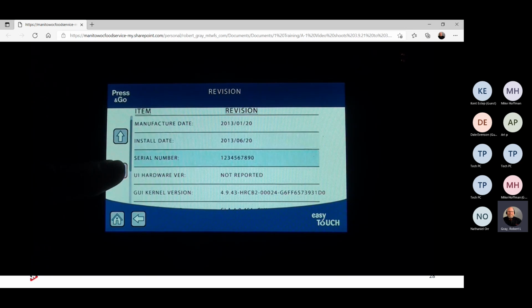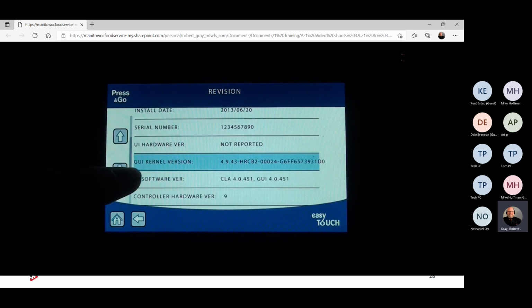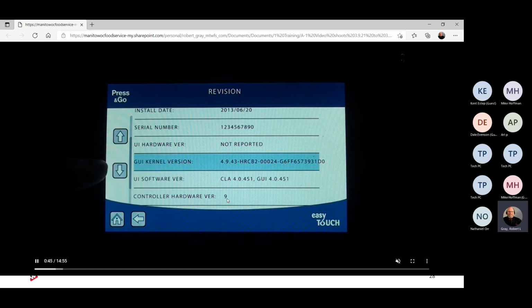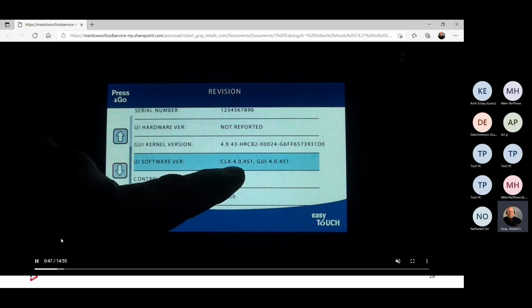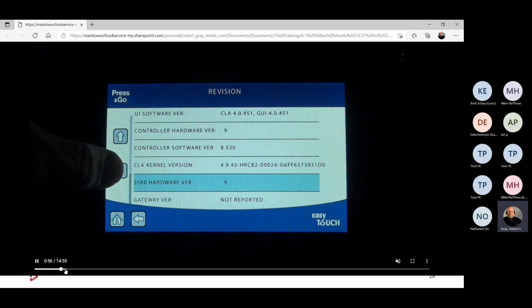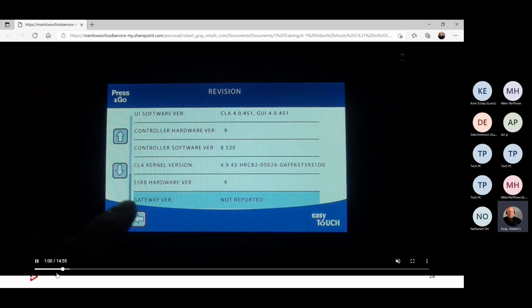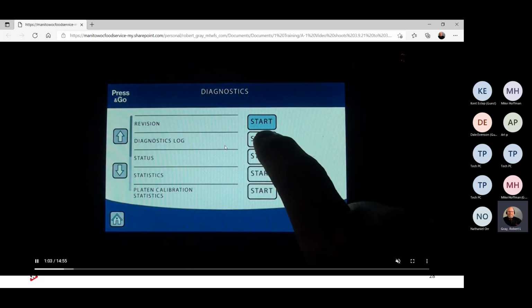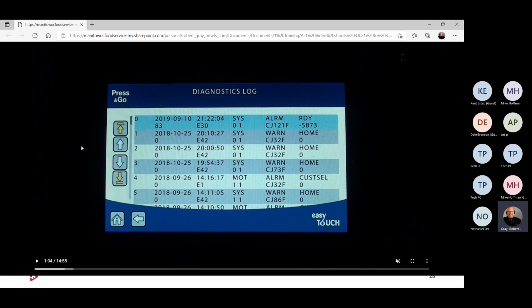Serial number, you're going to check the serial number. Is it correct? Yes or no? If it's not, you have to change it. Again, just all the different kinds of things going on inside here under revisions. Okay, I'm going to go back and we'll hit diagnostics log. All right, diagnostics log. Again, this is what we're going to use to diagnose this equipment. Remember when I said I can show you how to diagnose a solid-state relay board within 15 minutes? You're going to have to use the diagnostics log to help with that.